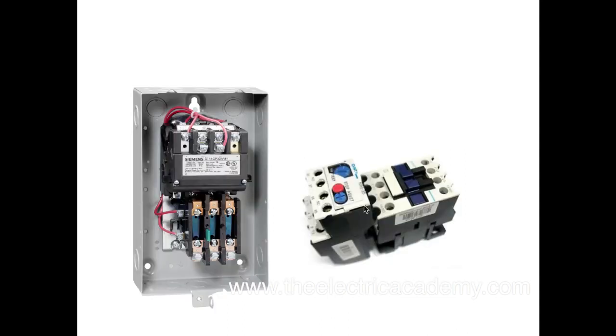Just to show you a couple different starters: this is a NEMA starter, so it's a bit more robust, used in North America. We're seeing a lot more of this kind going away, but basically you're bringing your three lines in on the top, three lines out on the bottom. You have your L1, L2, L3 coming in there, and then on this side you have T1, T2, T3 running off to the motor.